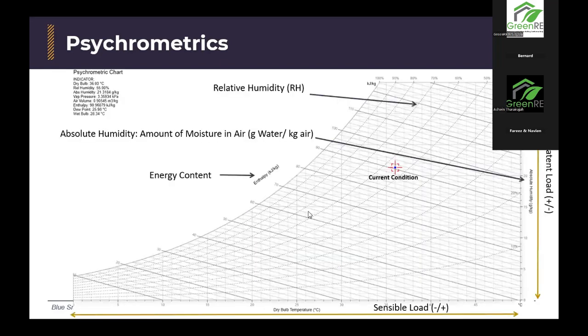Okay, so what is the psychrometric chart? There's a few things here. The first one is the RH, the relative humidity. Think of it as moisture in the air, but there's also something else called the absolute humidity, sometimes known as humidity ratio. These two may confuse people because they're both ratios of moisture to the air. But what's the difference? Absolute humidity, or humidity ratio, is the weight of moisture, or moist air, with respect to the weight of dry air.